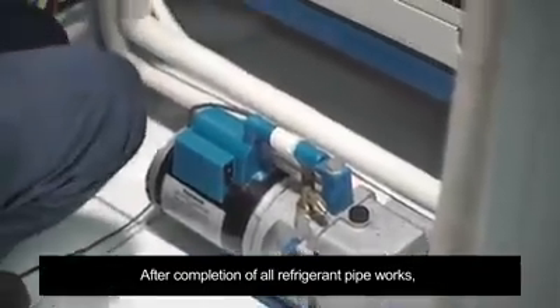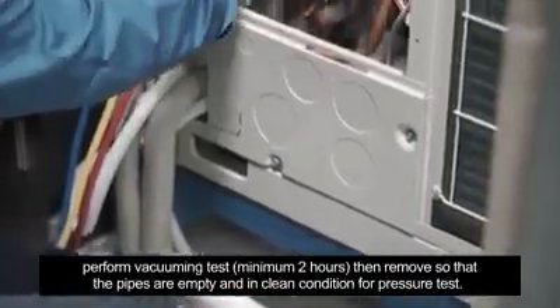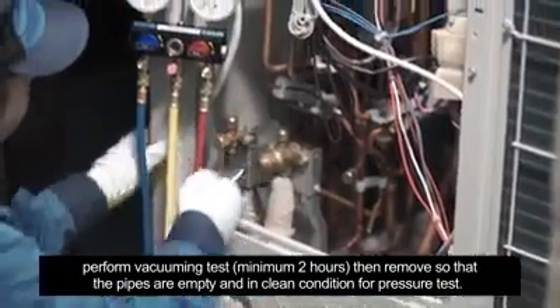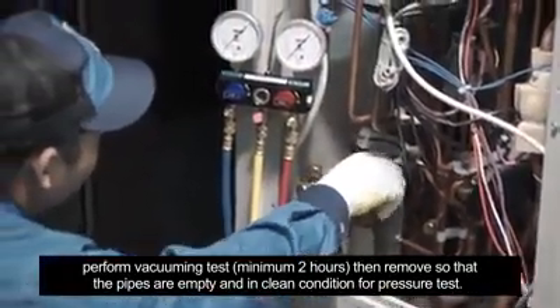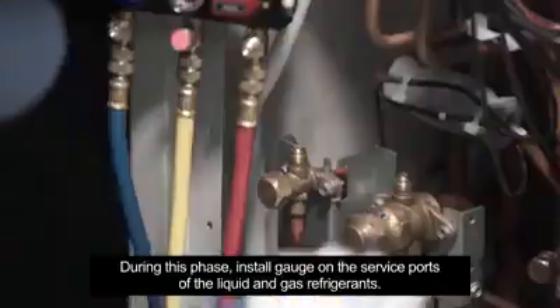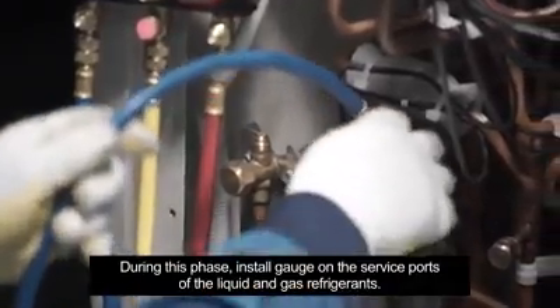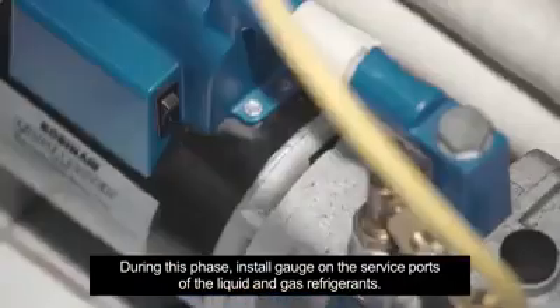After completion of all refrigerant pipe works, perform vacuuming test, then remove so that the pipes are empty and in clean condition for pressure test. During this phase, install gauge on the service ports of the liquid and gas refrigerants.